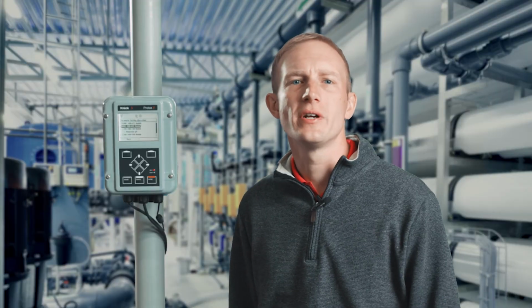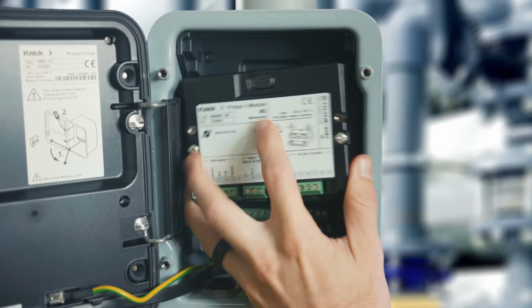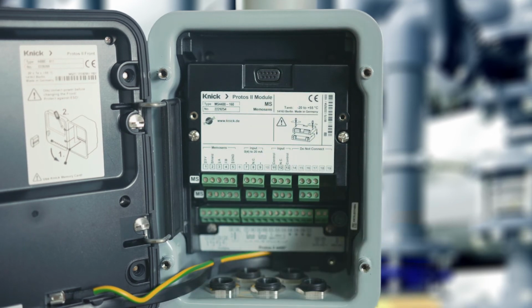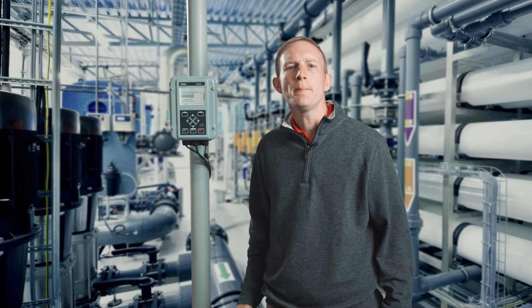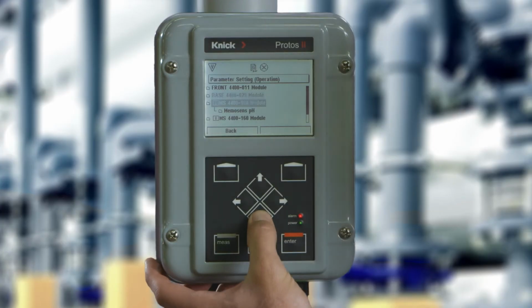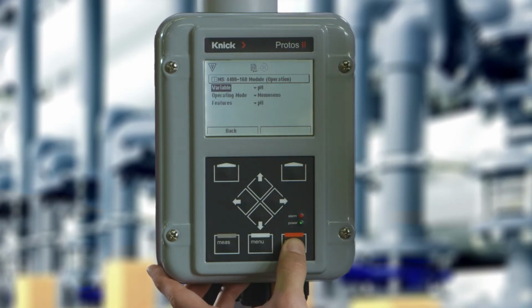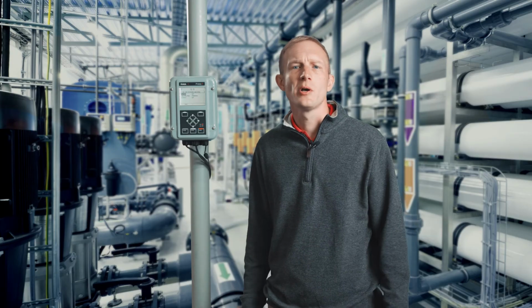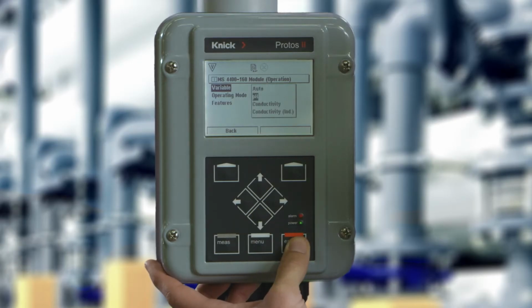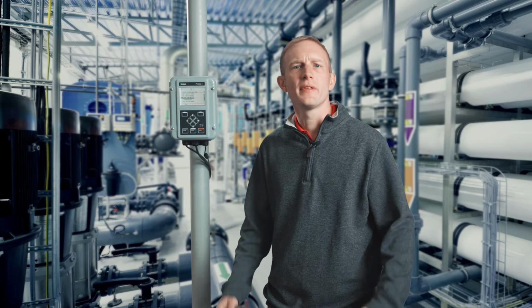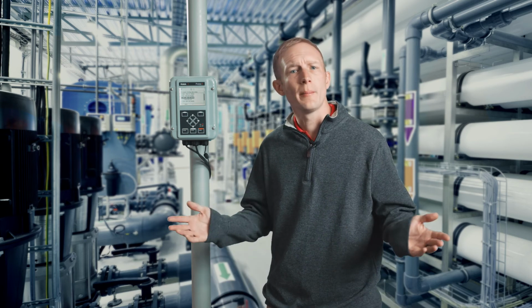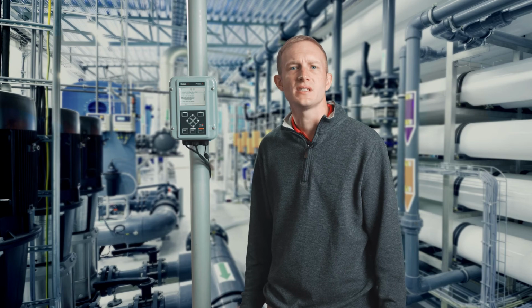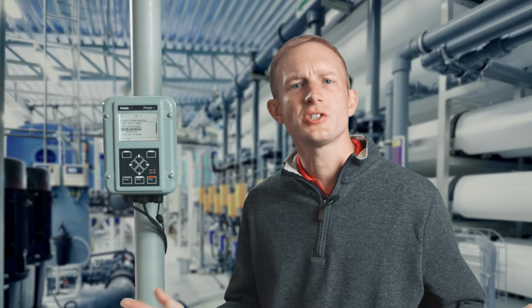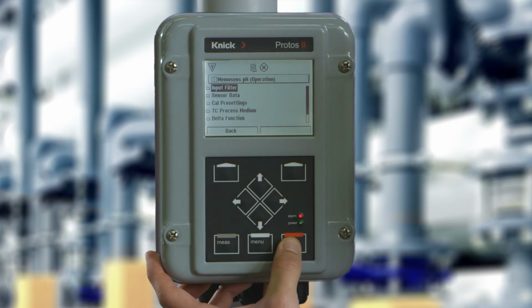The Protos 4400 is capable of taking in up to 4 MemoSense sensor inputs with the appropriate measuring modules installed. By selecting the input module, we can configure the process variables for both channel 1 and channel 2. Since both sensors are MemoSense sensors, we can select auto recognition for the process variables. Lastly, you'll want to ensure that the calibration settings are set up for both the MemoSense pH and MemoSense conductivity sensors. To do this, we will first select channel 1 for MemoSense pH. Here, scroll down to Cal Presettings and press Enter.